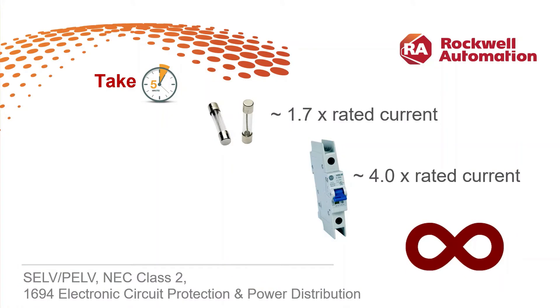As we just learned, these mechanical devices require significant overcurrent to trip. And one more consideration: in the AC world, relatively infinite power is assumed to provide that overcurrent. In the low power world, it is very likely that you didn't oversize your power source enough to trip the protected device, and thus you are not protected at all.